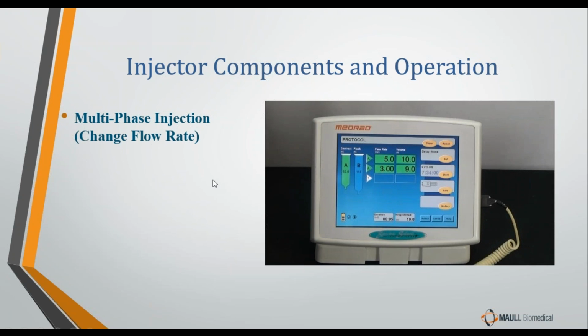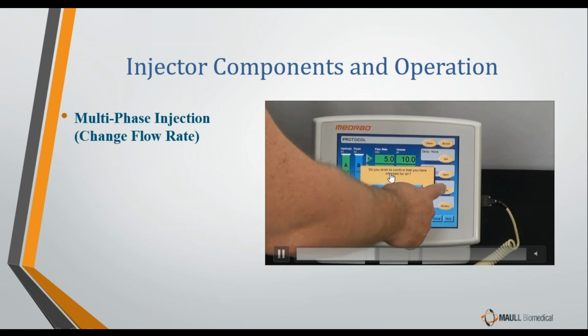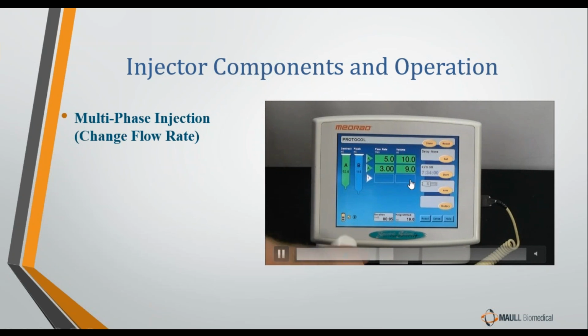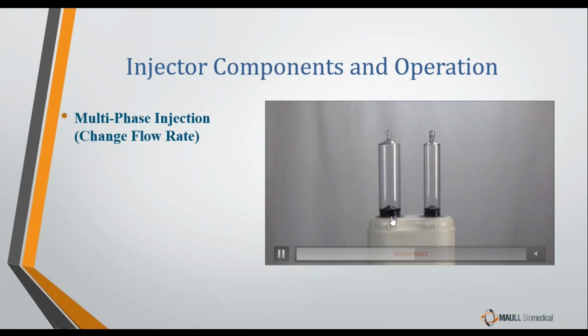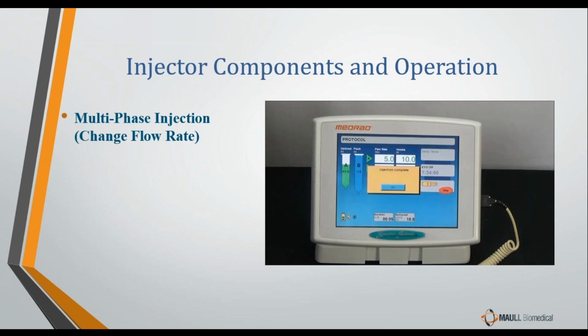Now, multi-phase injection, if we want to change the flow rate, notice that here we have 2 rows, phase 1, phase 2. Notice they are 2 different flow rates. We want to start off at a flow rate of 5, then we want to move to a flow rate of 3. So we're going to slow the injection down. It starts faster, then it slows down. That is a multi-phase injection if we wish to change the flow rate in the middle of the injection. We can increase the flow rate or decrease the flow rate. It doesn't matter. But to do it, we need to program a multi-phase injection, in this case a 2-phase injection.